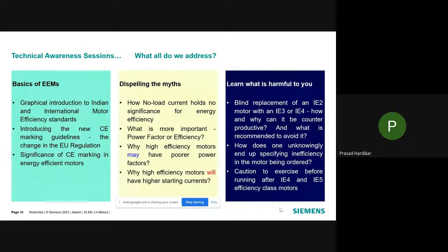Then we also have a session on dispelling the myths, where we talk about how a higher no-load current has no significance whatsoever for energy efficiency. We address a very common fallacy: which is more important, power factor or efficiency? Most of the time people favor power factor because it shows a reduction in current drawn, but that does not contribute to efficiency. So we clarify that particular myth.